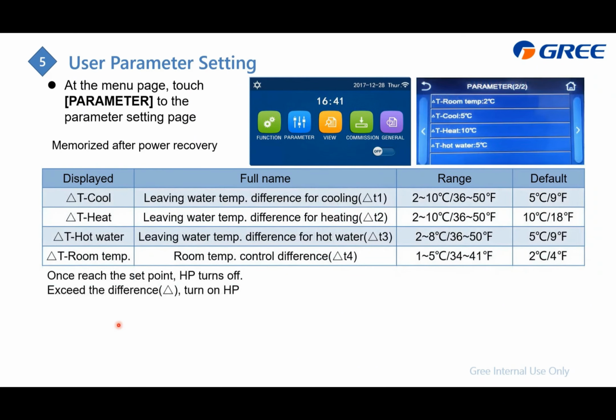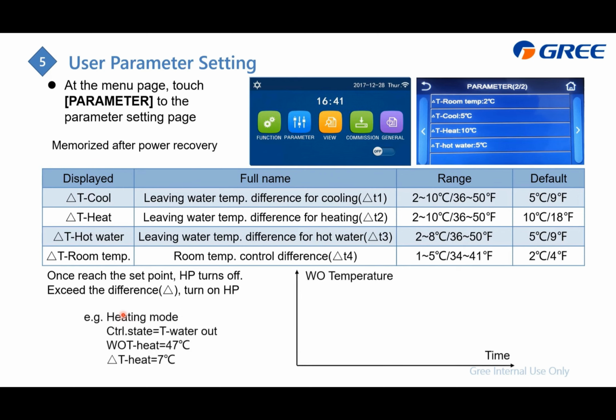On the second page is to set the delta T for cooling, for heating, for DHW, and also for T room. And this delta T means once it reaches the set point, the heat pump will turn off. And after that, if we detect the difference between the detected value and the set point exceeds the setting value, we will turn on the heat pump. So I will show you an example to explain.